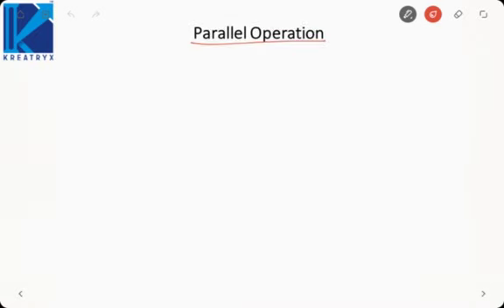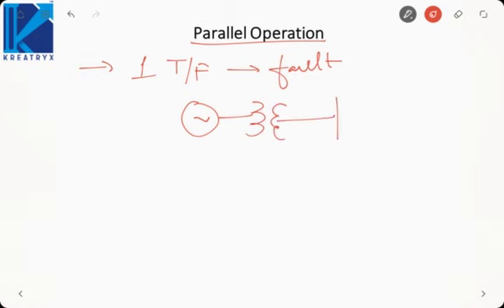So parallel operation is nothing but there are more than one transformers, usually two transformers, that are connected in parallel. Now why they are connected in parallel is because suppose only one transformer is there which develops a fault. Now usually power transformers are connected something like this. This is my generator, this will be my transformer, this will be my transmission line. Now what happens if this transformer develops a fault? No power will go from generator to the transmission line. So whatever the loads are connected here, all loads will get switched off. Okay, entire unit will be switched off, so all the loads will get switched off.